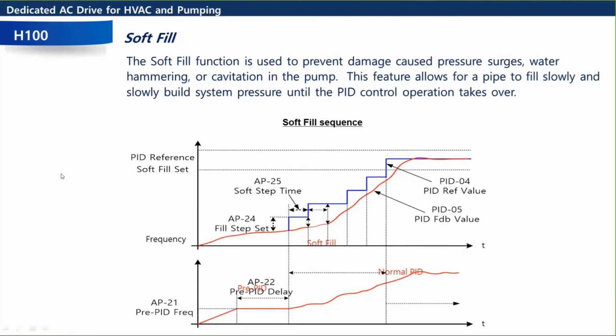It's going to run as fast as it can to build up the pressure, because pressure is going to start out at 0. So soft fill is a way to slowly fill the pipes and prevent those things from happening. It slowly builds up system pressure until you reach a certain level that you program, and then it switches over to regular PID regulation.